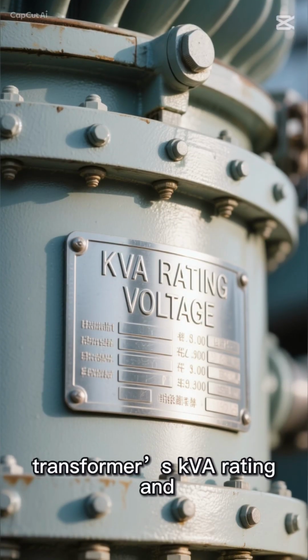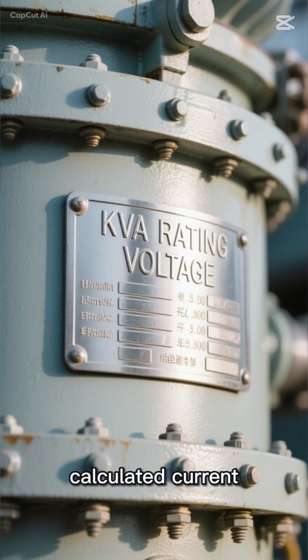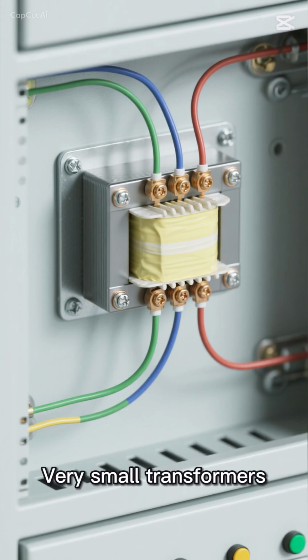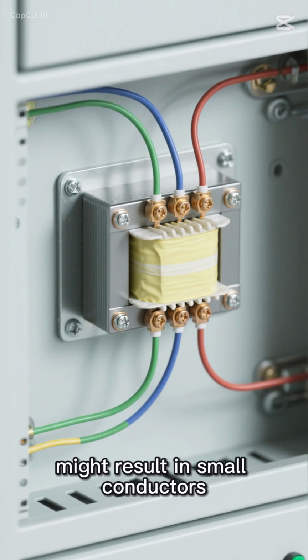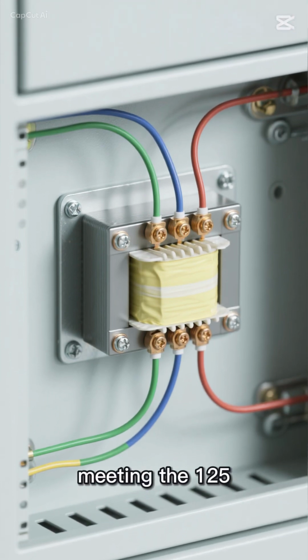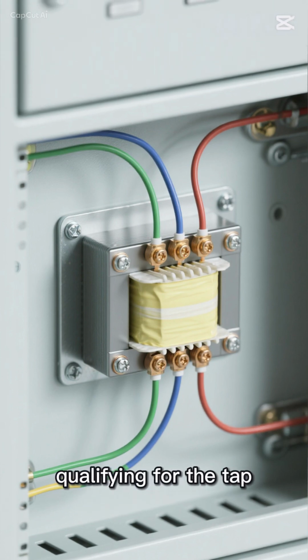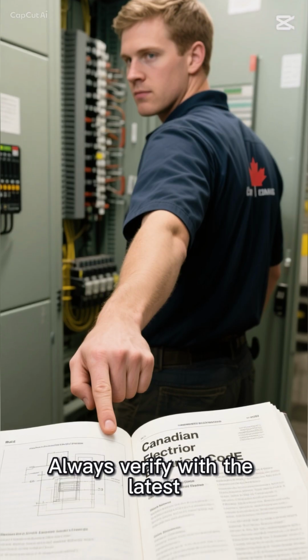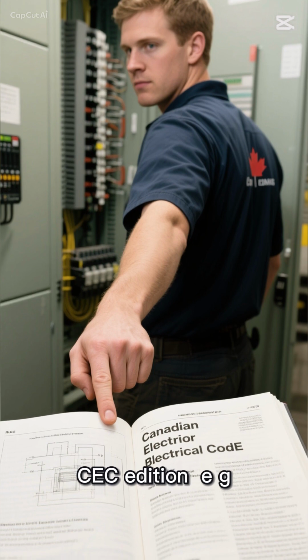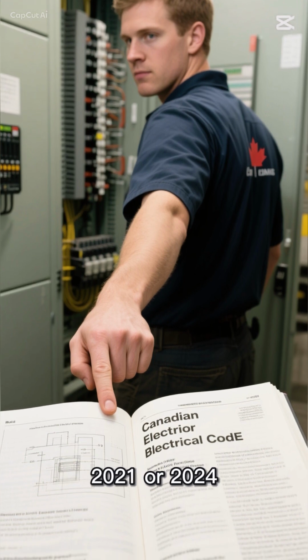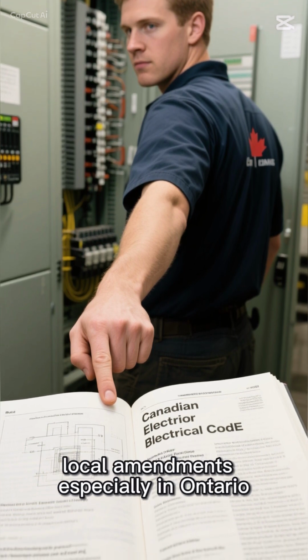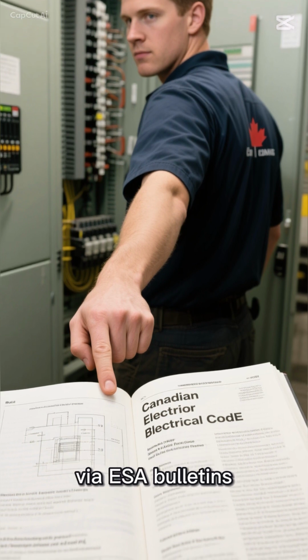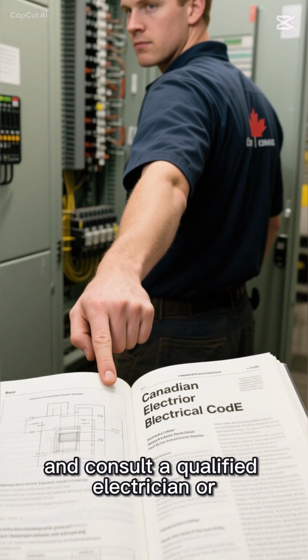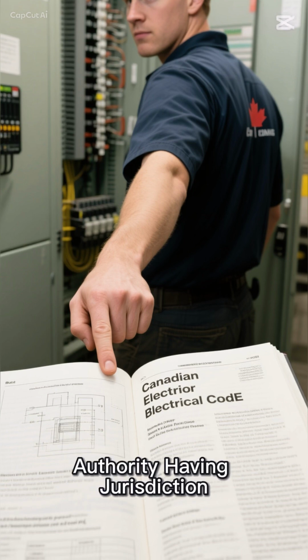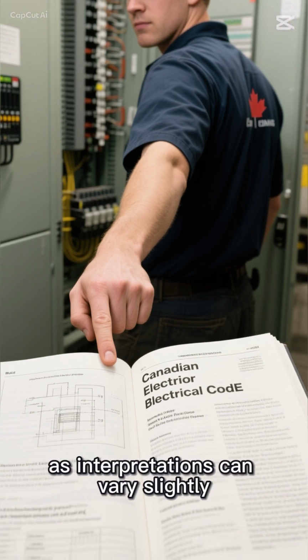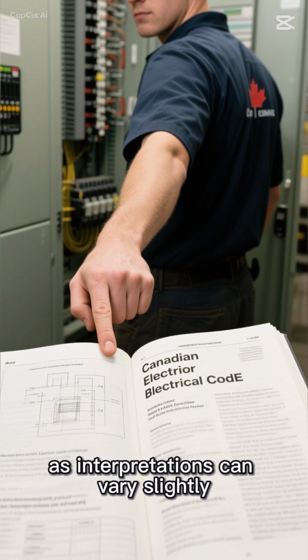It depends on the transformer's kVA rating and calculated current. Very small transformers might result in small conductors, but always at least meeting the 125% ampacity, unless qualifying for the tap exception. Always verify with the latest CEC edition, e.g., 2021 or 2024, local amendments, especially in Ontario via ESA bulletins, and consult a qualified electrician or AHJ, authority having jurisdiction, as interpretations can vary slightly.